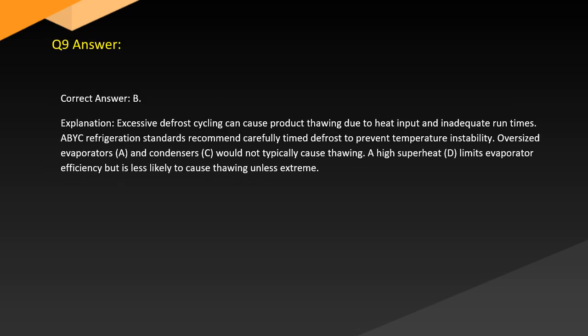Answer. Correct answer: B. Explanation: Excessive defrost cycling can cause product thawing due to heat input and inadequate run times. ABYC refrigeration standards recommend carefully timed defrost to prevent temperature instability. Oversized evaporators, A, and condensers, C, would not typically cause thawing. A high superheat, D, limits evaporator efficiency but is less likely to cause thawing unless extreme.